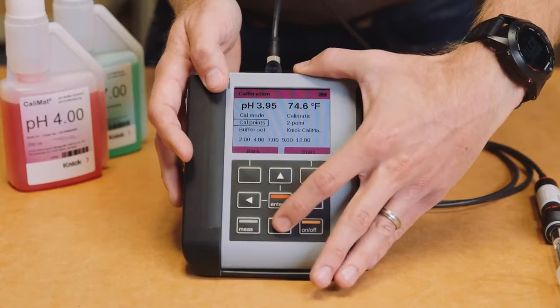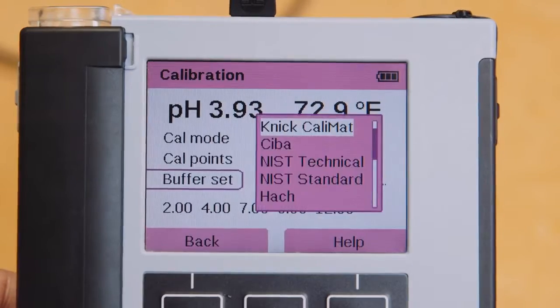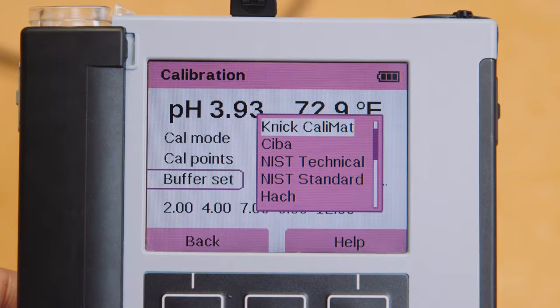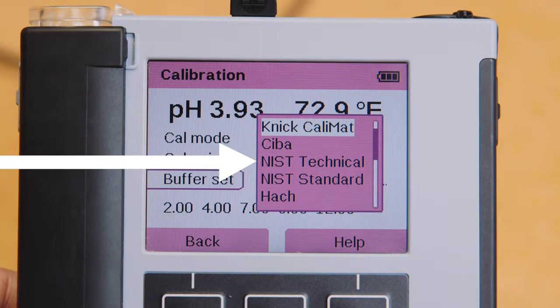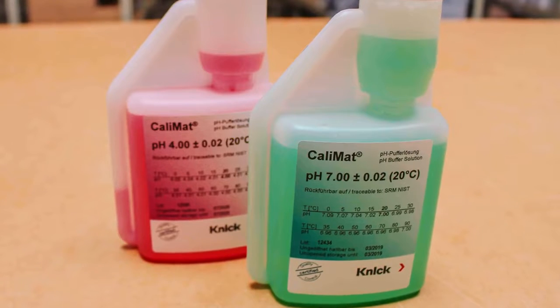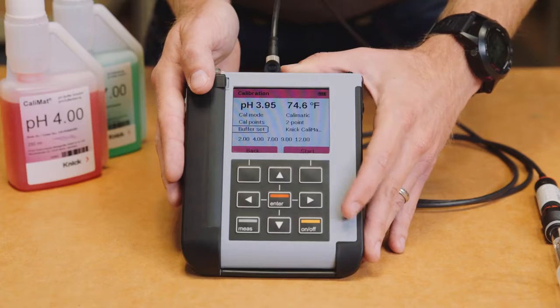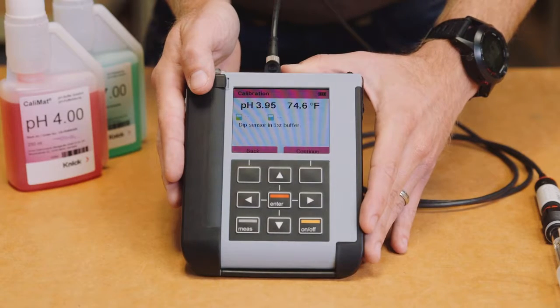You'll see that once you've selected Calimatic under the calibration mode, it then offers us the ability to select which buffer set we are using. When using Calimatic mode, the Portavo is preset with 10 common buffer sets to choose from. All are pre-programmed with temperature compensation tables. It should be noted the most common buffer on the market is NIST Technical. You can verify your buffer set by checking the labeling on your bottles. Next, press the upper right button to start the process.